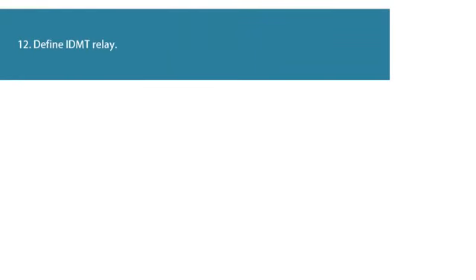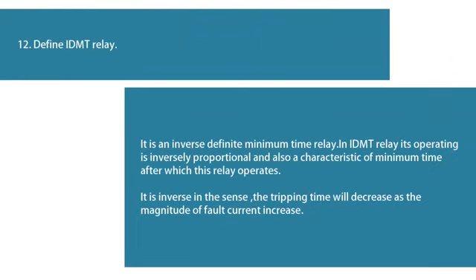Question 12: Define IDMT relay. IDMT stands for inverse definite minimum time relay. In an IDMT relay, its operating time is inversely proportional — it also has a characteristic of minimum time after which the relay operates. It is inverse in the sense that the tripping time will decrease as the magnitude of fault current increases.